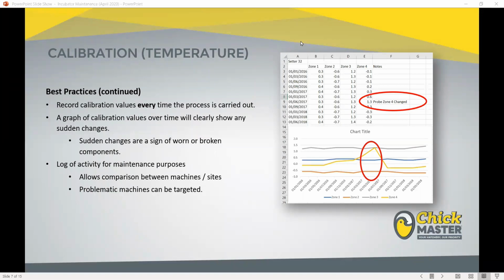Right. For wet bulb probes in a multi-stage machine, would it be better to calibrate around the running range or around the dry bulb? Or is around the dry bulb okay? So if it's a wet bulb probe, you're absolutely fine calibrating it to a dry PT100 calibration box. So if it's a wet bulb humidity probe, you can take the wick off and calibrate it that way. That's absolutely fine. If you're asking about calibrating dry humidity, there's two options.